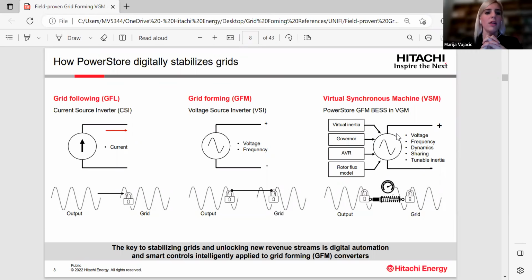It operates quite well and stable when the network is strong, but it has some challenges in the context of weak network conditions, because it relies on PLL, and then the system might experience problems with synchronization to the network when the network is weak. To overcome those problems or challenges, we developed grid forming. Grid forming is voltage source inverters, which provide voltage and frequency references, and the current is defined by the loads or the fault. This control mode enables good operation in the context of off-grid systems, but has some challenges when operating in parallel with other generators.